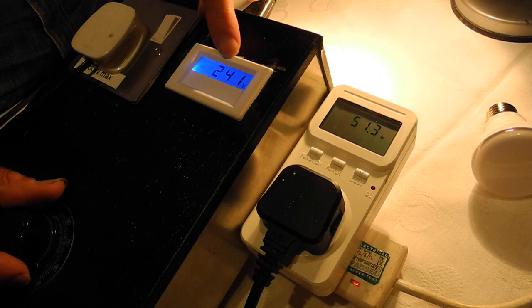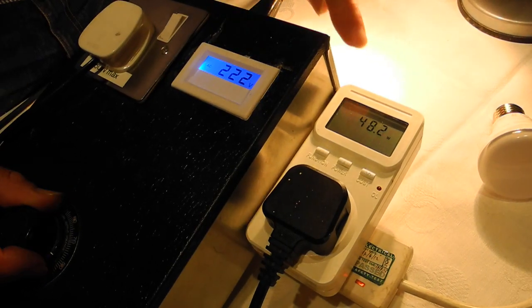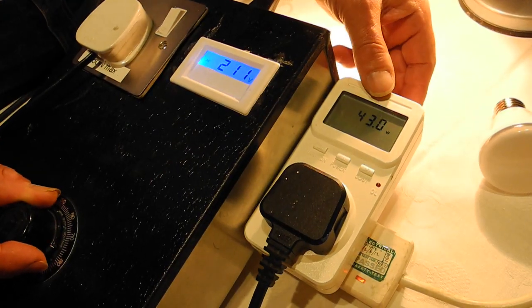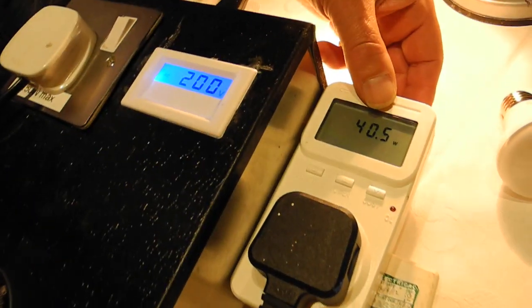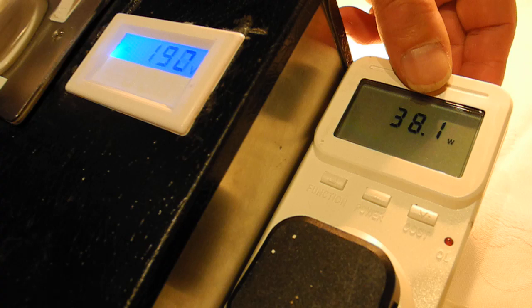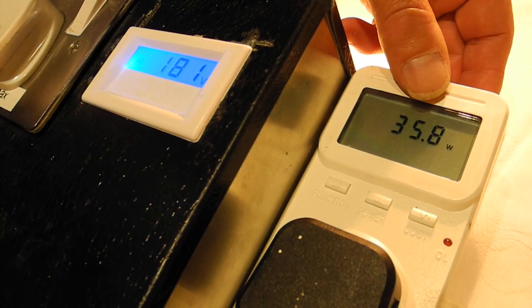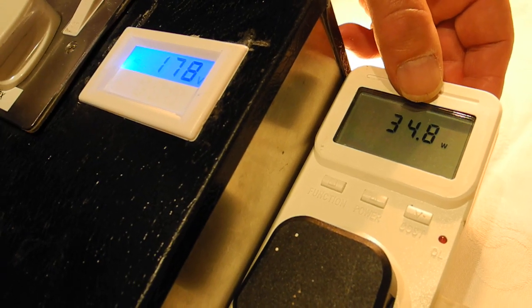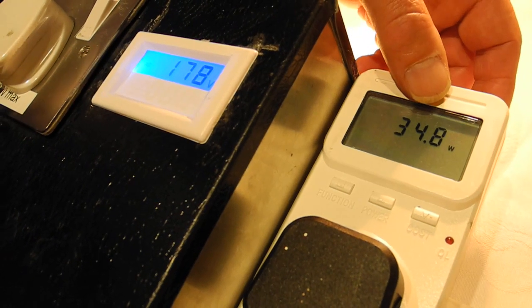Now when I reduce the voltage we are taking it down past 220. If you watch what happens on the power meter you'll see that the power drawn reduces as the voltage goes down and I'll take it right down to 180 volts so that you can see the effect of an extreme voltage reduction. There we are, we're down to about 35 watts compared with over 50 when we were operating at full voltage.